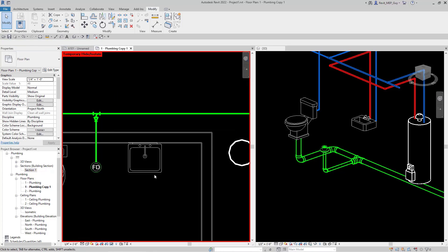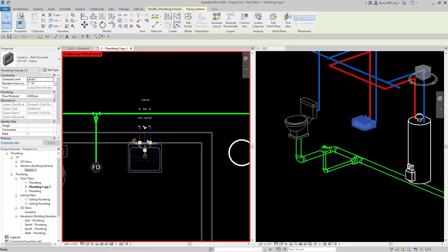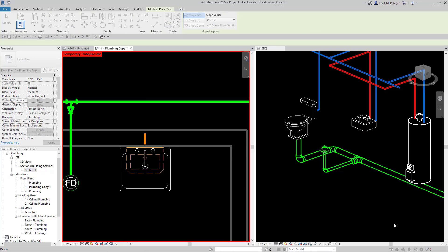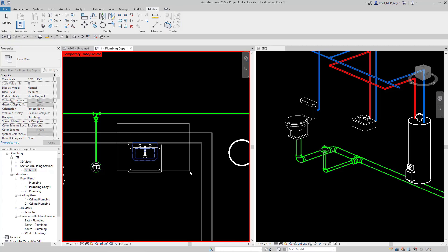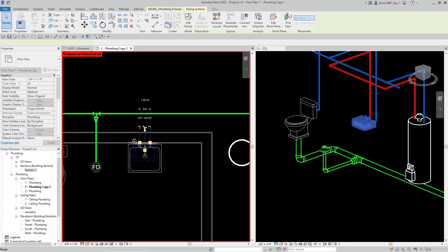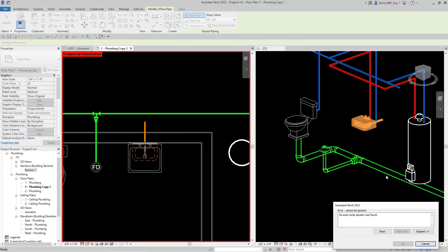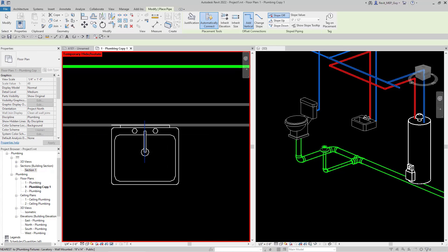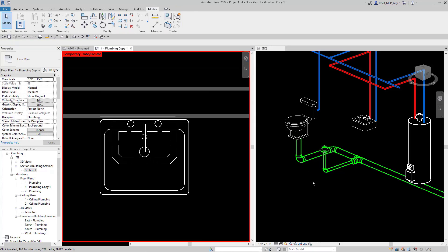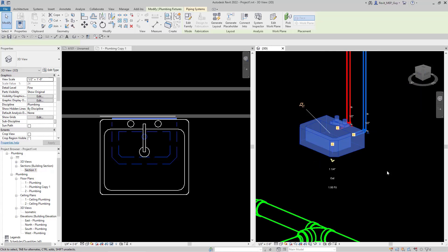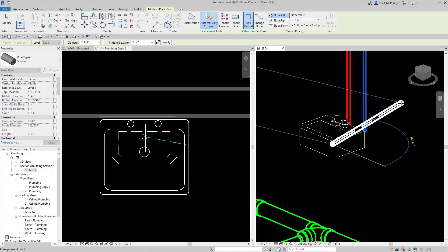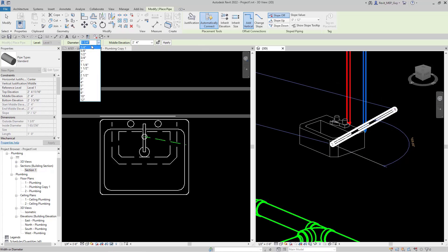For my lavatory I'm just going to hover over it and select it — maybe a crossing selection — and start the pipe for the sanitary system. Revit is telling us we didn't draw it far enough. Let's try that again and select the lavatory. Revit isn't liking that because the starting point is actually at this drain right here, so we have to pay attention to where the pipe is being drawn from. If I select it in the 3D view and start drawing, it's coming out of this drain location, so we can't go off 90 degrees — we have to drop it first. Let's drop it to about 18 inches.